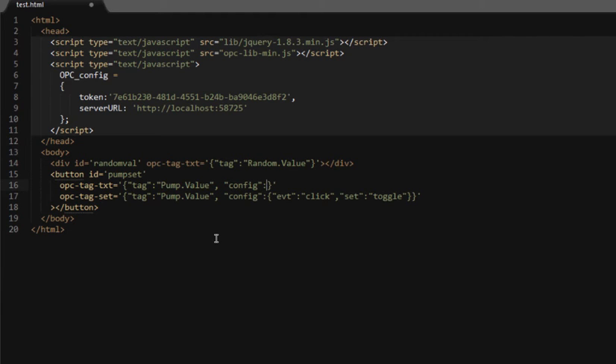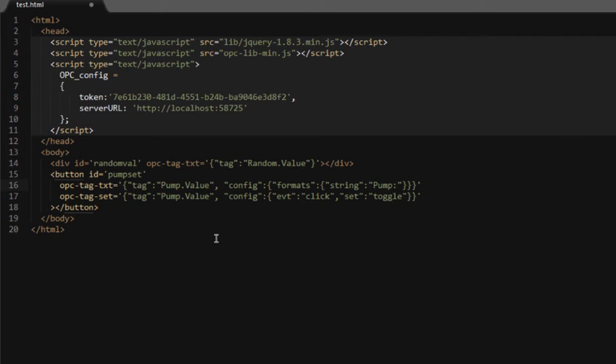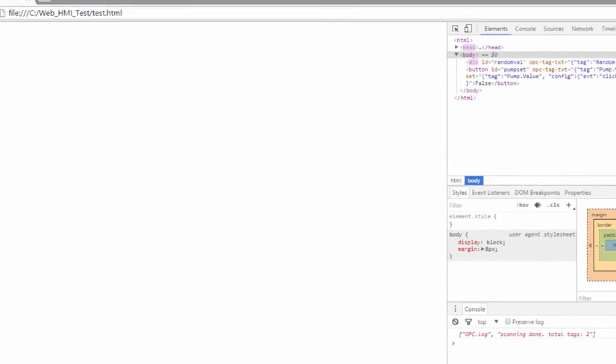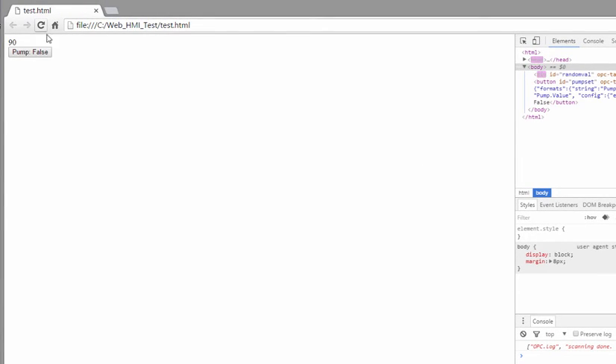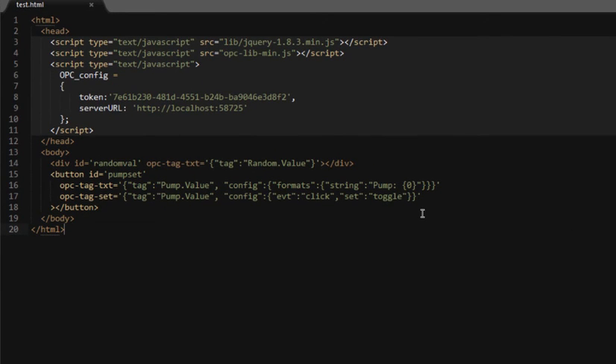But in most cases, we want to have something a little bit better than just the raw true or false value showing up in the button. We want to format that text so it displays something more meaningful. We're going to add a config to this opc tag text, and add a formats element. In the formats, we're going to add a key of string, because we're formatting a string. Then we can type any text we want and put a placeholder. In this case, I'm just going to write pump colon, and then put a placeholder of curly braces with a zero. That'll be the place that the value coming from pump.value is going to be inserted. So we get a formatted string. Whenever we change that value, you see that placeholder gets replaced with the real value.